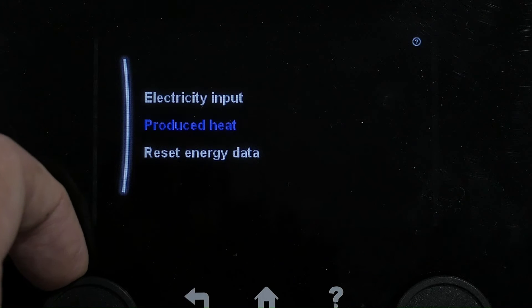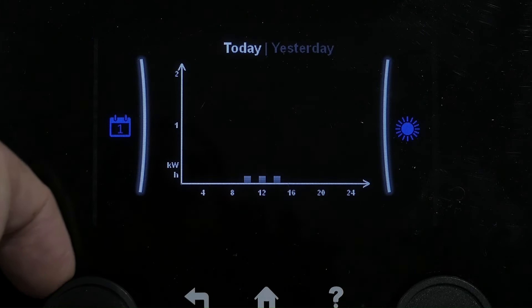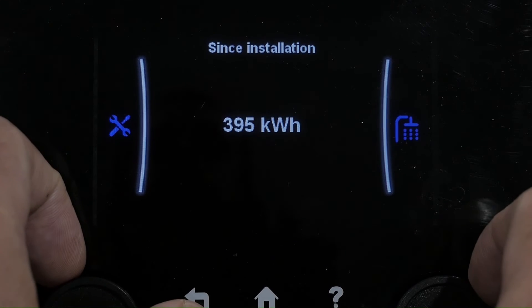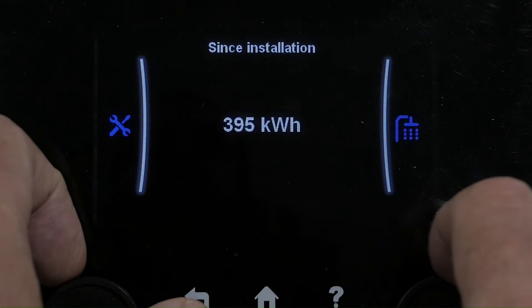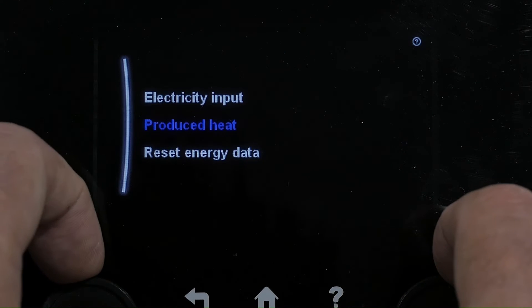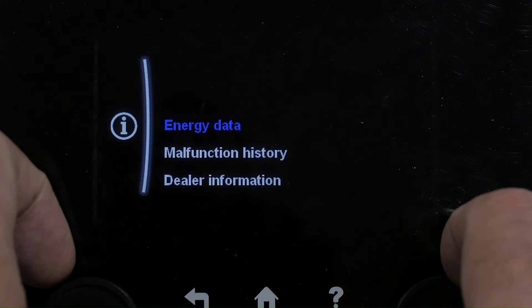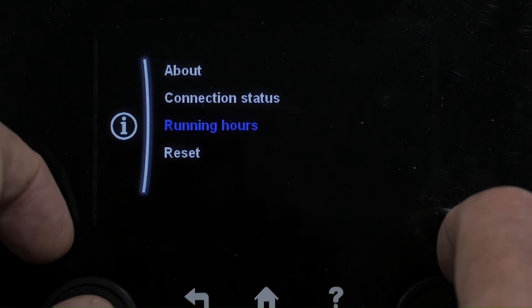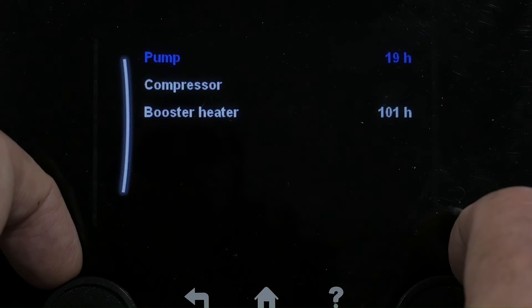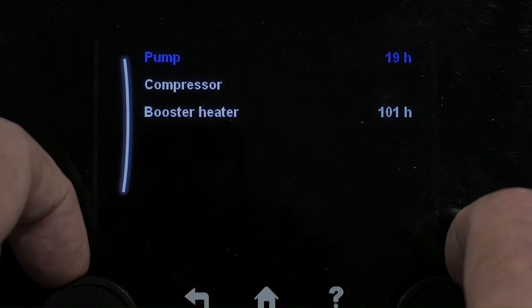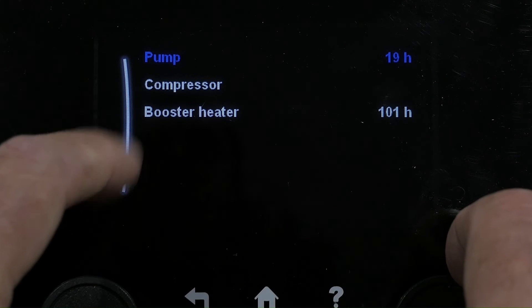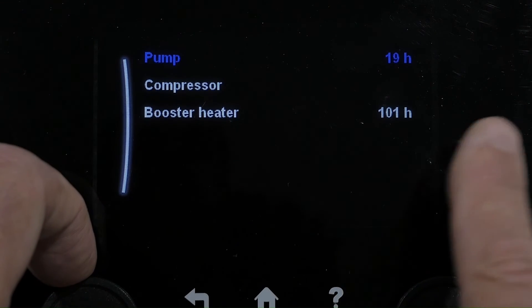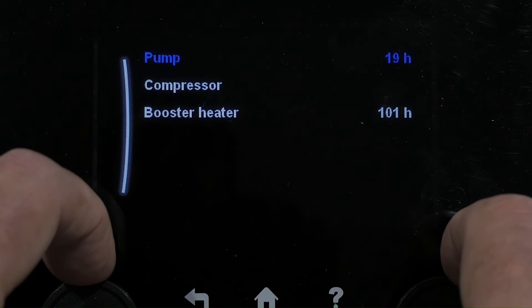You can also look for the running hours on the electricity input screen. Here we can see the pump's been on for 19 hours, and the compressor and booster heater have been on for a long time. This helps give you an indication if you've got poor running costs as to what's going on.